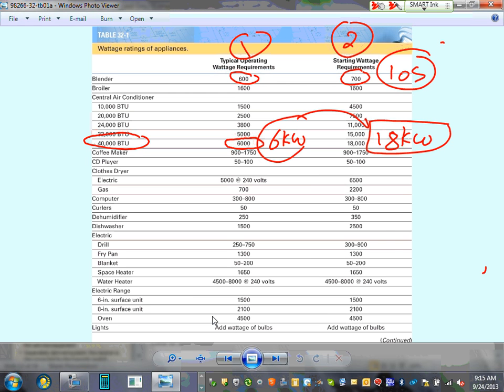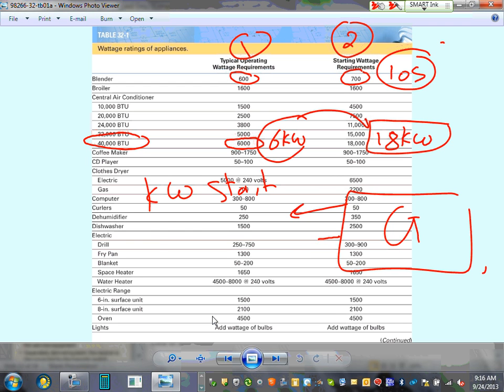So when you size your big generator, guys, it will have two sizes. It will have kW start, and it will have kW run. You want to make sure your generator can run all the loads that you have and can start all the loads that you want to start at the same time. Typically, the start is 2 to 4 times more than the run. Any comments, any questions?